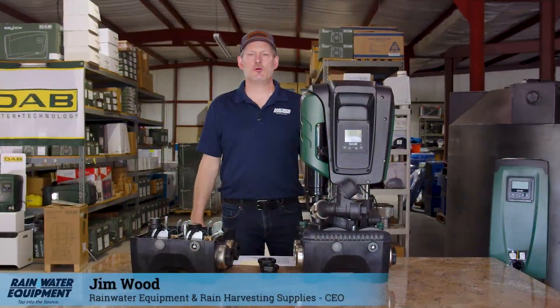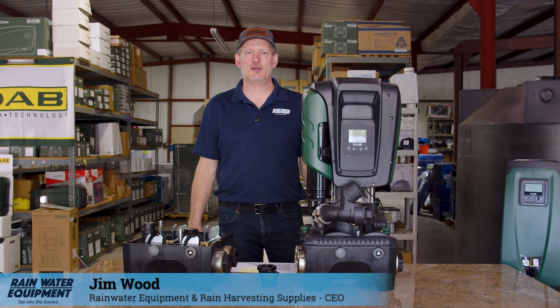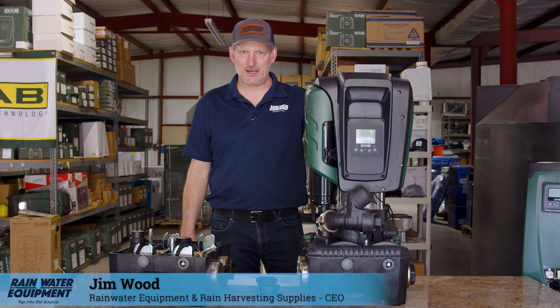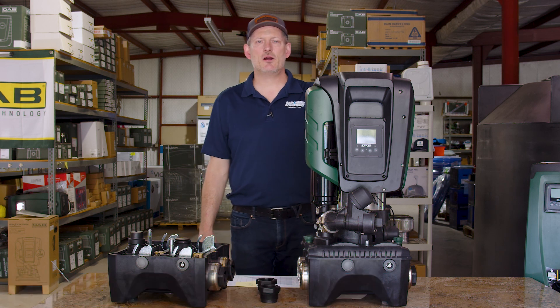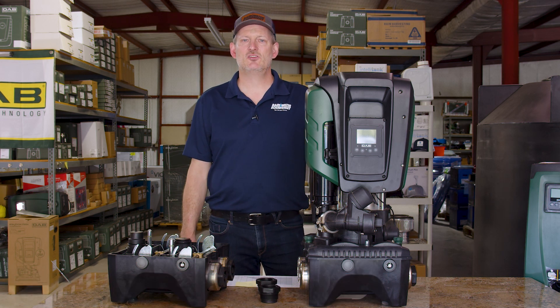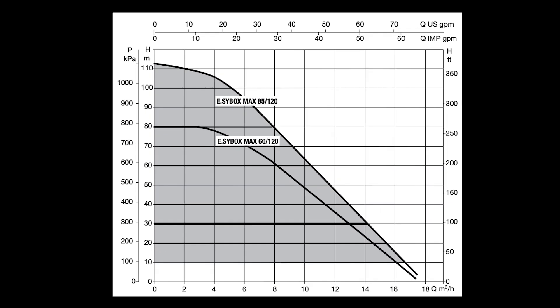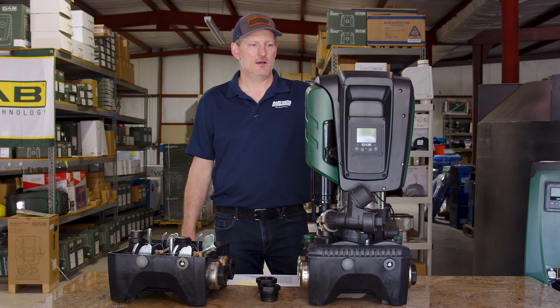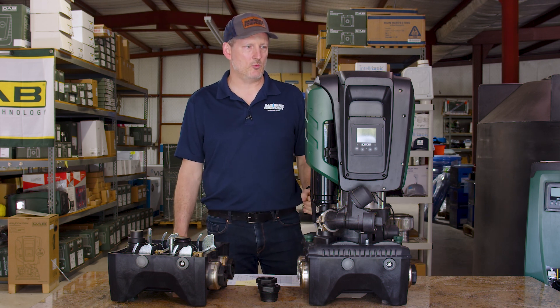Hey guys, Jim at Rainwater Equipment and Rain Harvesting Supplies. Today I'm talking about the Esybox Max from DAB. The Esybox Max is a constant pressure variable speed pump system capable of 40 gallons per minute at 75 PSI, 50 gallons per minute at 55 PSI, and 60 gallons per minute at about 35 PSI. It is a high-flow, constant pressure pump with a VFD drive.